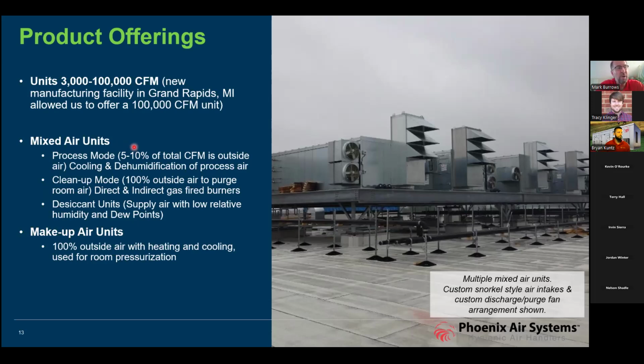That bad air, by the way, in the hallway consists of 2 things that can go wrong for us. It could be full of bacteria. It also could be at the wrong dew point. So if your room's 45 degrees and you're bringing in 65-degree hallway air, that air will condense wherever it can inside the building. So again, 5 to 10% outside air is usually sufficient. Keep in mind, on 45-degree process rooms, it's 10 tons per 1,000 CFM.